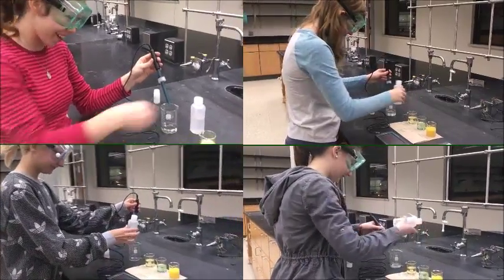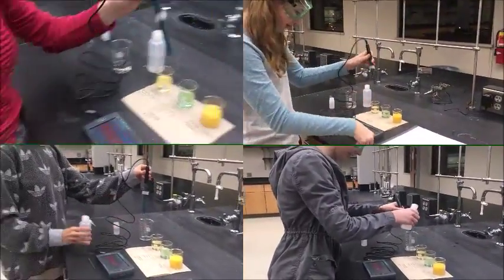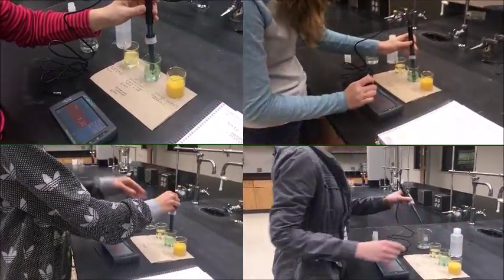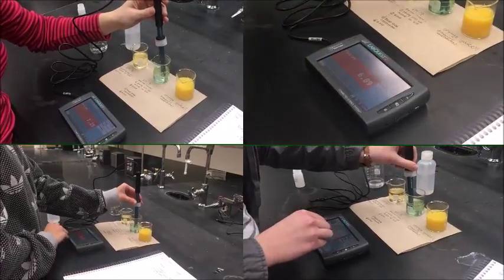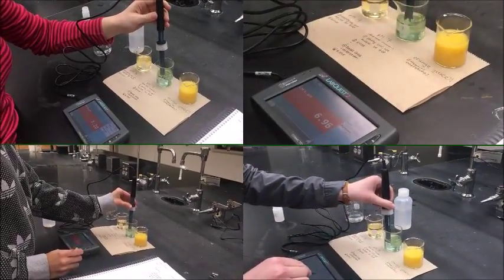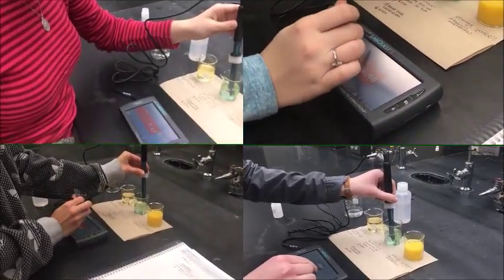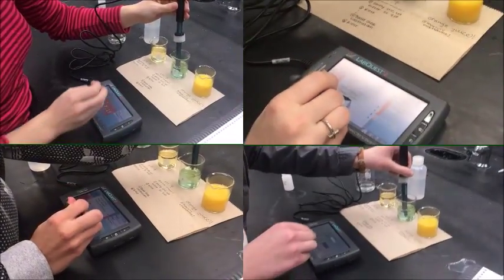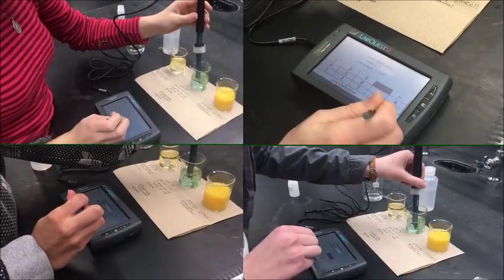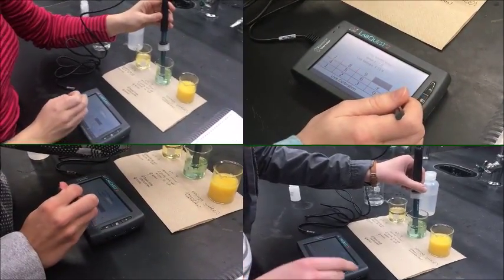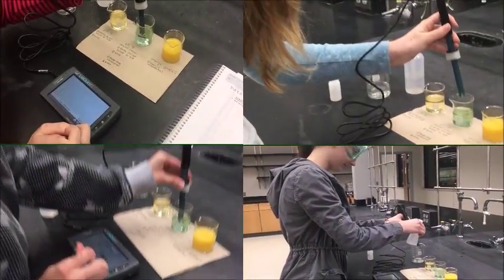The first step in calibrating your pH meter is to remove the electrode from the storage solution and then rinse it with DI water. Next, you put the electrode in the pH 7 buffer solution and you gently stir. Then on your LabQuest, go to Sensors, then Calibrate, and then Calibrate Now, and wait until the voltage stays constant. Then you're going to adjust the pH reading to 7.00 for the buffer solution and press Keep.